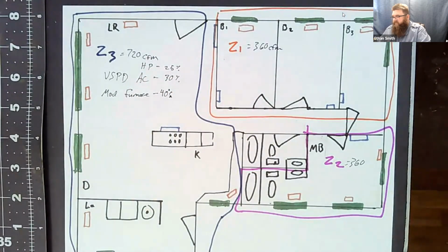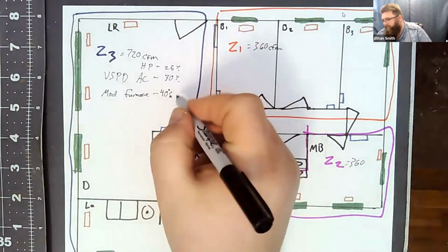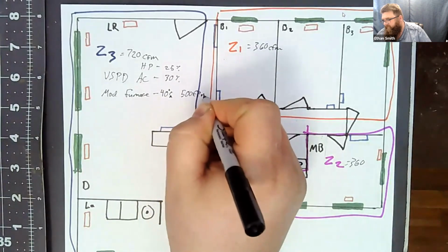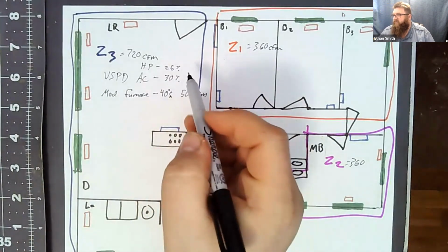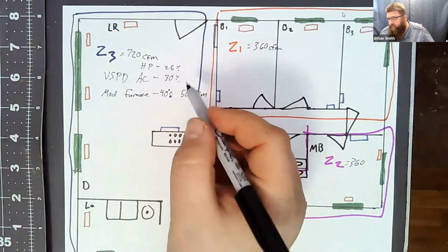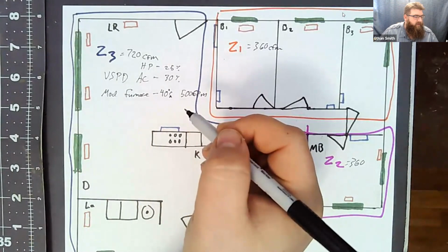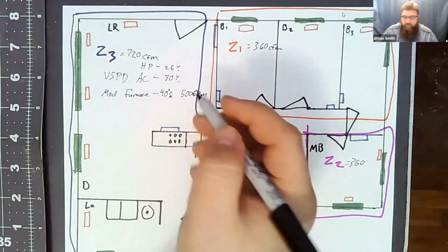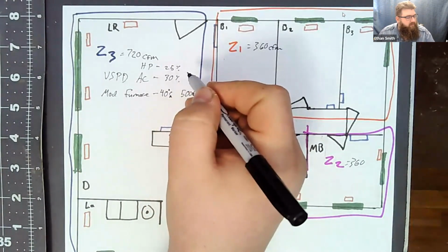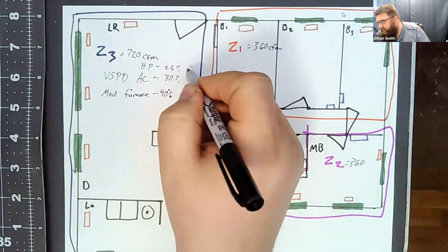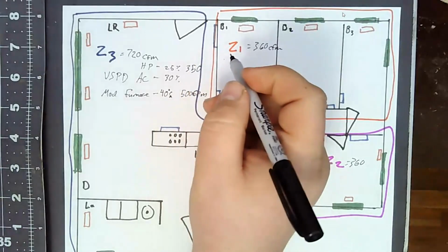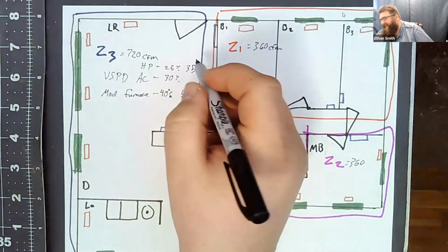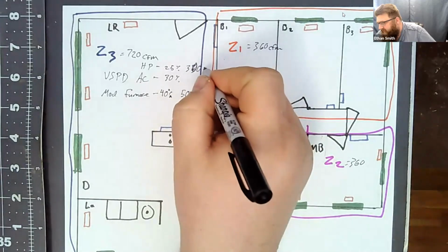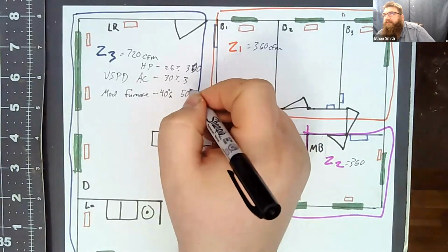Okay, so let's translate that into airflow numbers. So 80,000 BTU modulating furnace at 40% is going to need approximately, let's see here, 500 CFM. Okay, my variable speed AC at 25%. We'll call it a heat pump for rounded numbers. So 25% of 1200 is going to put me at 350, I think. Close. Yeah, 300, ain't it? It should be, yeah, it is 300 because 3 times 4 is. We'll call it 300 CFM. Thank you. I can math today. 30% would be about 330.